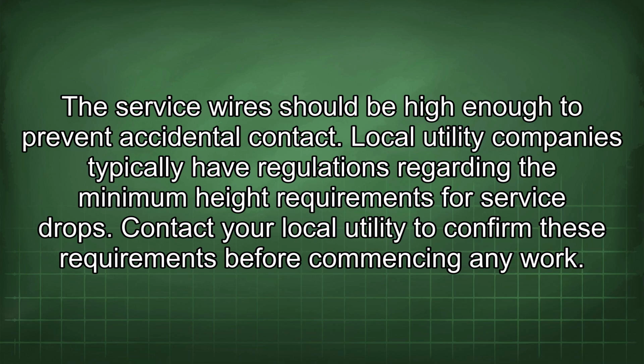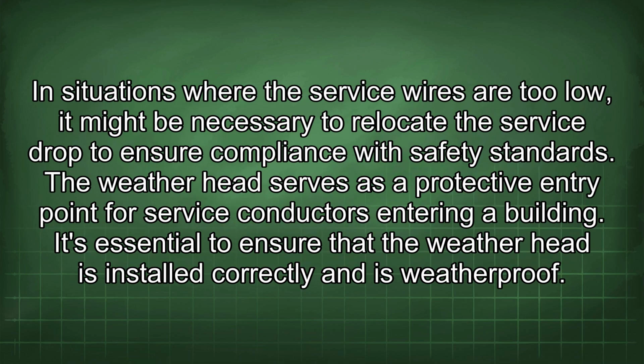Local utility companies typically have regulations regarding the minimum height requirements for service drops. Contact your local utility to confirm these requirements before commencing any work. In situations where the service wires are too low, it might be necessary to relocate the service drop to ensure compliance with safety standards. The weatherhead serves as a protective entry point for service conductors entering a building.